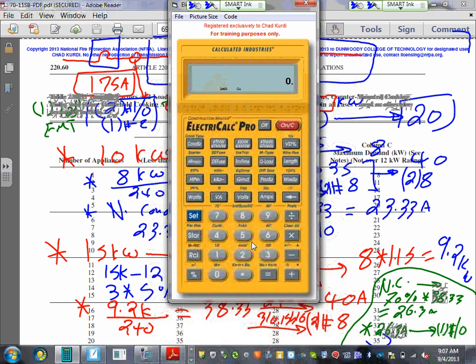Here's my number 8 wire size. Copper, everything is copper. 2 conductors, THHN. Okay, and I have number 10 wire size. How many of them do I have? 1 conductor, and the insulation is THHN. And you have to click again. That will give you the total. The first click gives you the cross-section area of one of them. The second click adds it up. And then you click here and it gets you a 1/2 inch. You could have said that from the get-go, 1/2 inch.